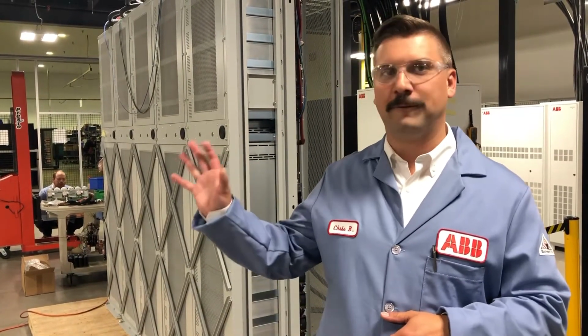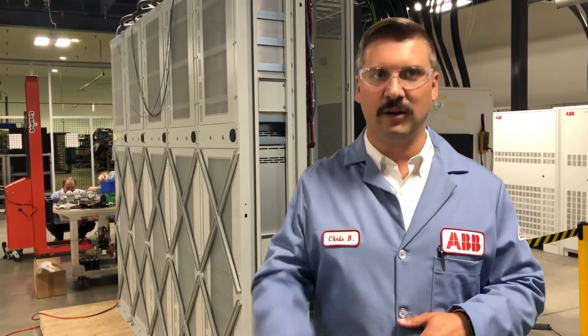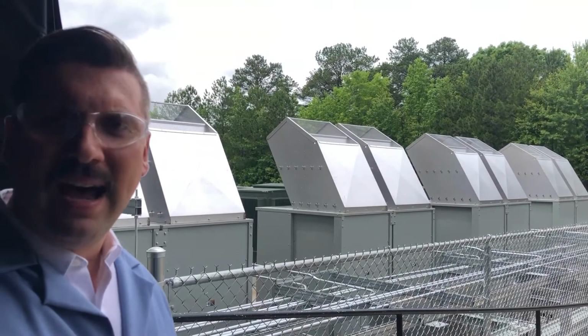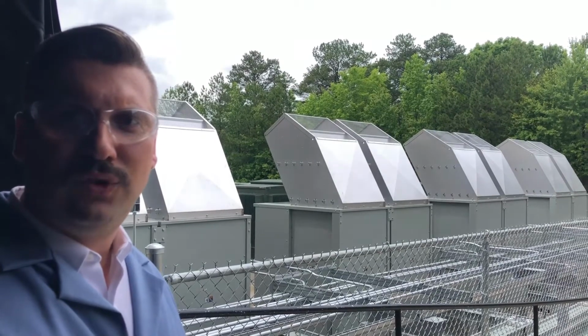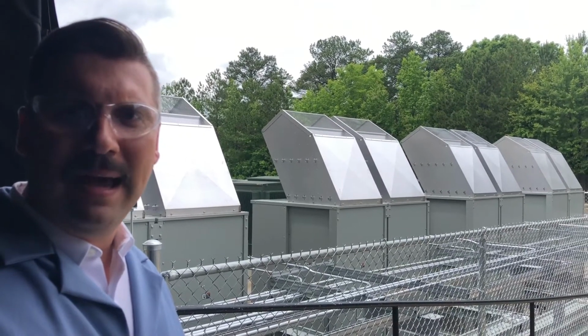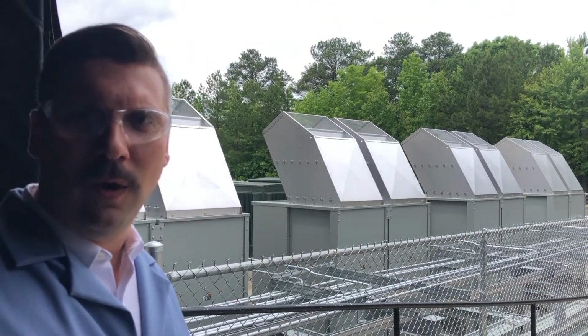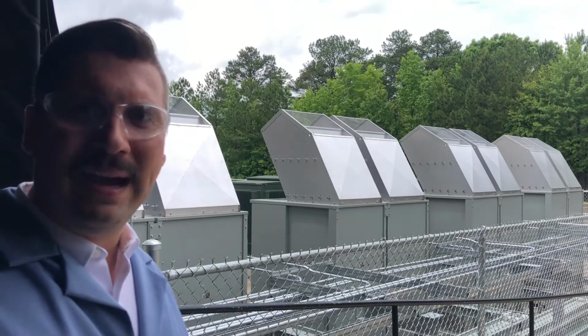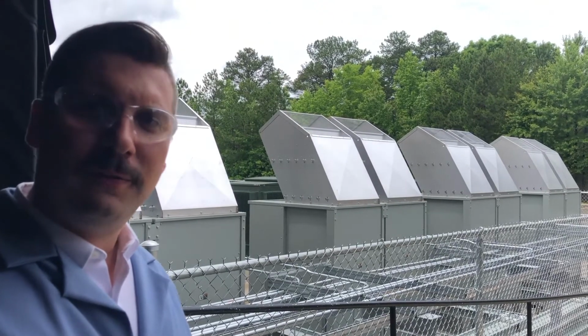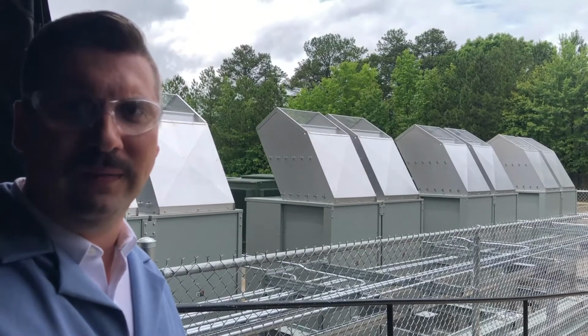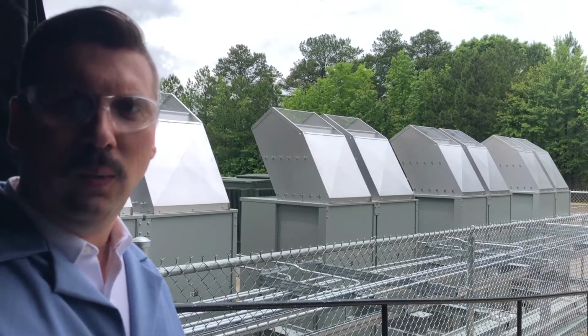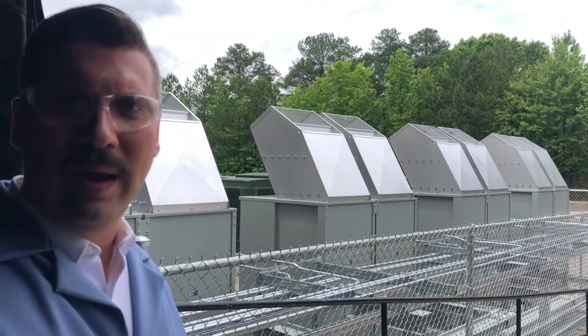At this point, we're going to transition and just talk a little bit about the infrastructure we have in place for this test center. Starting outside, we have our 2.5 megawatt service entry transformers and four 2 megawatt resistive load banks. For all of the power distribution we've done in our facility, we've used ABB busway products.